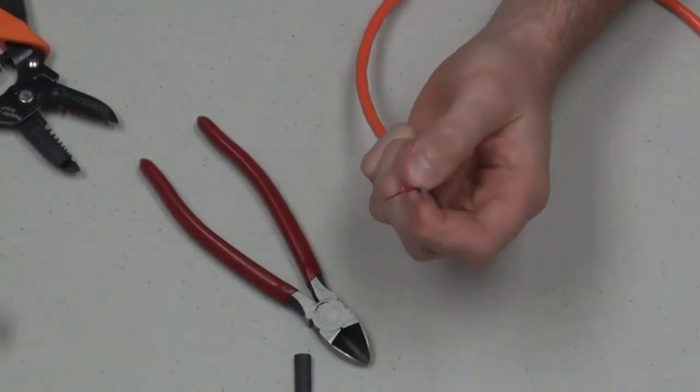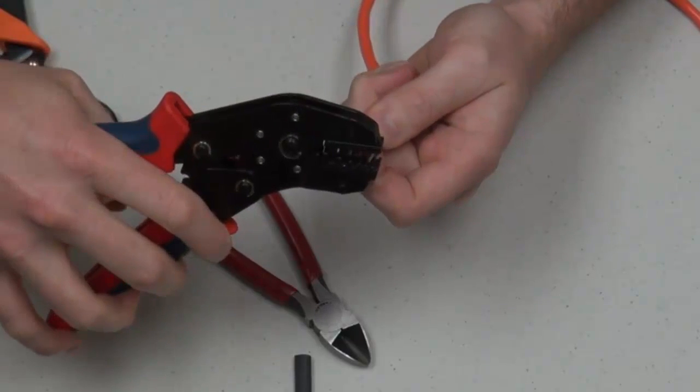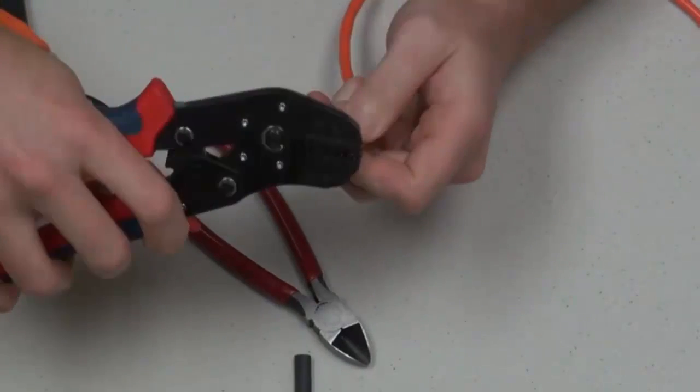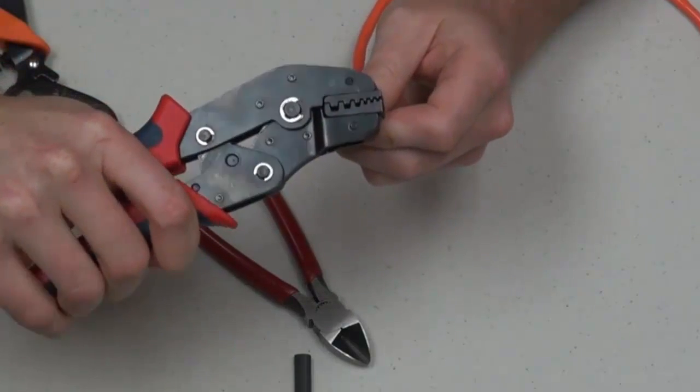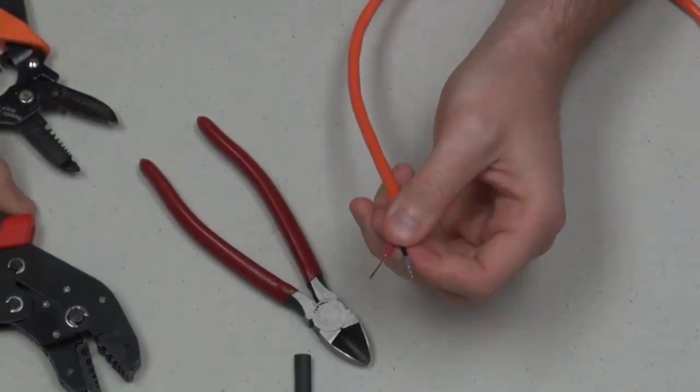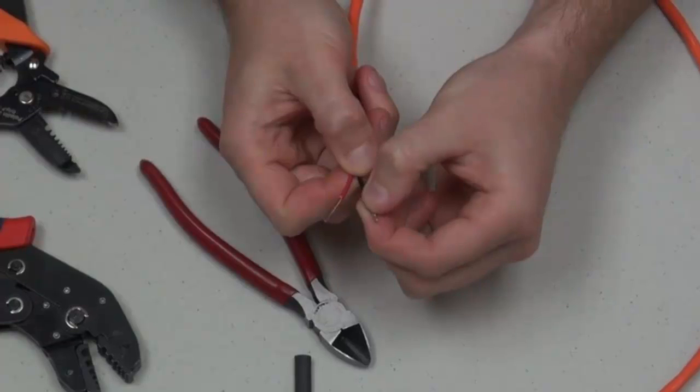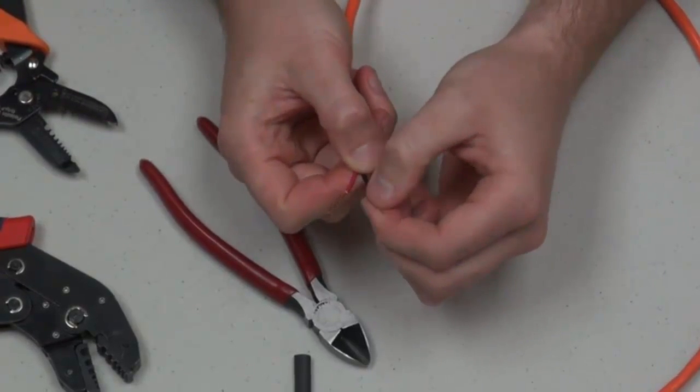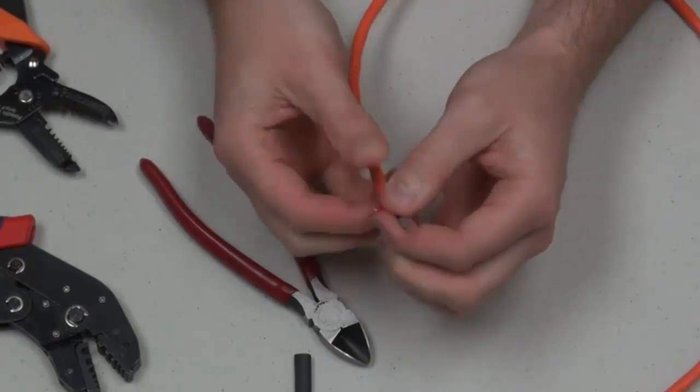The next step would be to take your trusty crimpers here. Put the ferrule inside the crimper of the appropriate size. Click down. You hear that click. It means it has notched nicely. And I like to also give it a nice tug. Pull on that. It shouldn't slide off. If it does slide off, you want to redo it and make sure you've got the right size and everything.